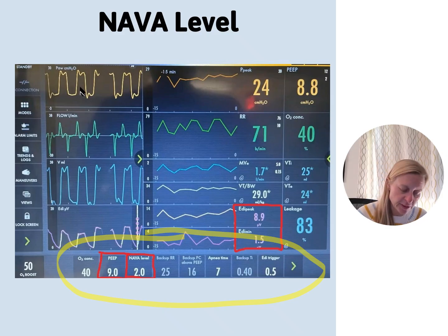Does everyone see what their NAVA level is? It's 2.0 there. So that's going to be on the outside of our parentheses. On the inside is going to be the peak minus the min. So you see the Edi peak there is 8.9. We're going to subtract 1.5 from that, close our parentheses, and then add our PEEP. Anyone see where our PEEP is? It's down here in this bottom corner, 9. So we're going to take 8.9 minus 1.5, which is 7.4. And we're going to multiply that by 2, which is 14.8.